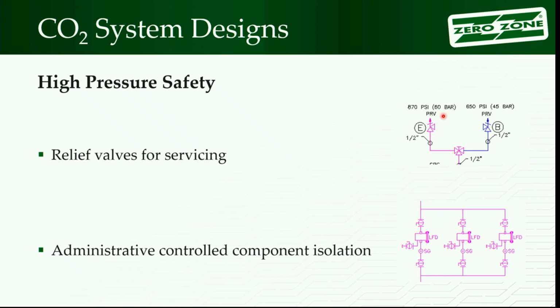So with that, that leads us to the next topic, administrative controlled component isolation. That's four big words. What it means is technicians need to be with their A game when they're servicing equipment. You need to be thinking, when I'm isolating segments for work, am I isolating liquid refrigerant? Am I isolating liquid and vapor refrigerant in there? And if I am, how am I going to drop the pressure down to a safe level? So this is a picture, we'll see the full drawing here. There's a big system, they had three liquid filter dryers on there. So you could isolate one of them, change it out, put it back in service, change the next one out.